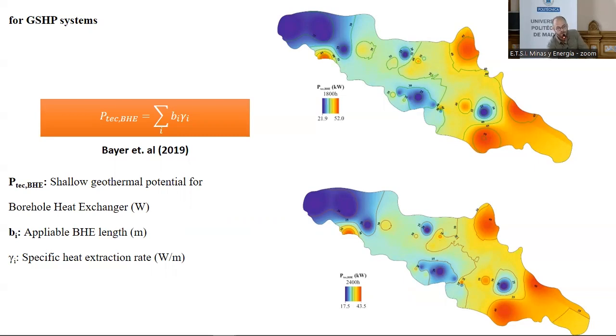P tec, BHE represents the shallow geothermal potential for borehole heat exchangers. A borehole heat exchanger is a vertical closed loop system—used when you don't have space in front of your building to lay pipes horizontally, so instead you install them vertically. For this vertical closed loop potential, you calculate it using this equation.